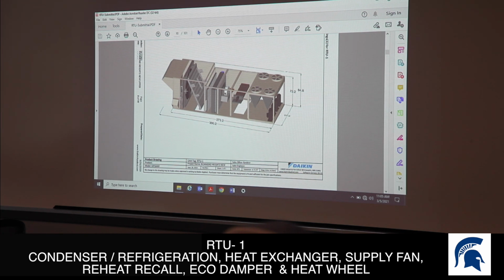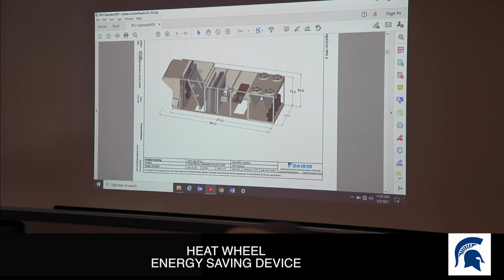Are you familiar at all with the heat wheel? No? Okay, what heat wheels do is they're an energy saving device. Typically in schools you have pretty decent requirements for outdoor air, so you're bringing in quite a bit, and you've paid money to condition what's in the space. So what the heat wheel does, and I'll show a better picture of it down the road, is it takes the air you're exhausting, passes it over the wheel, and that wheel absorbs the heat or cooling, depending on the season, and passes it to the entering outside air.